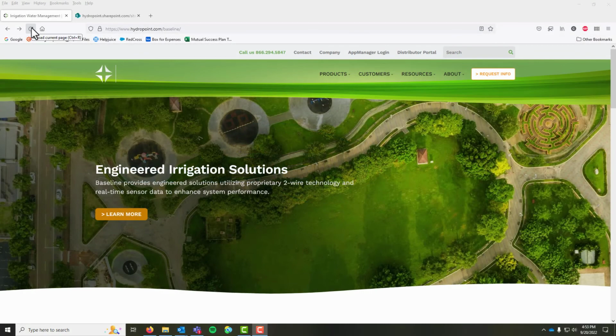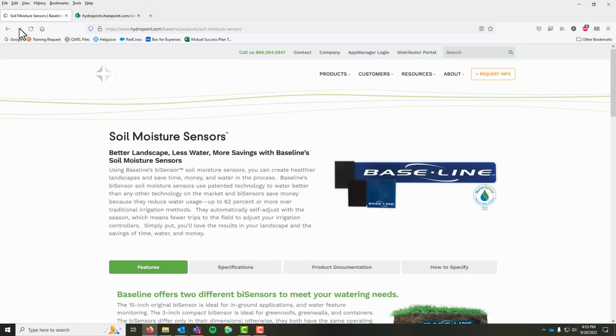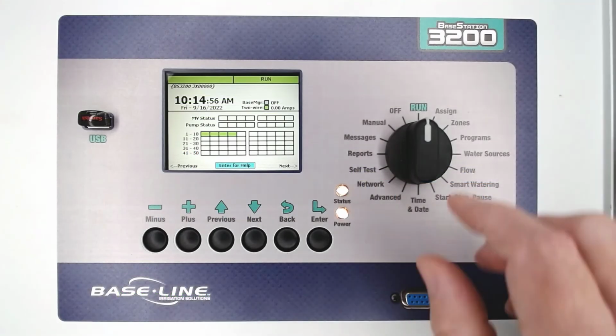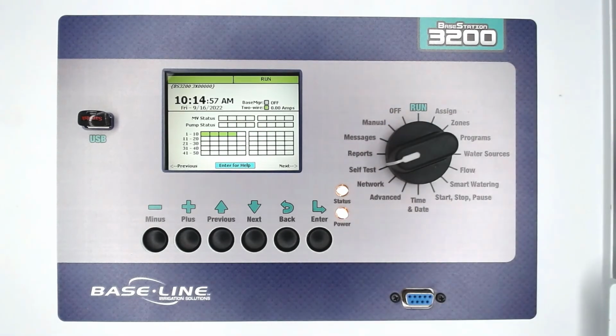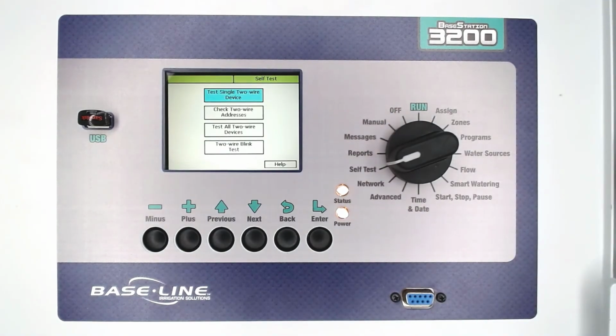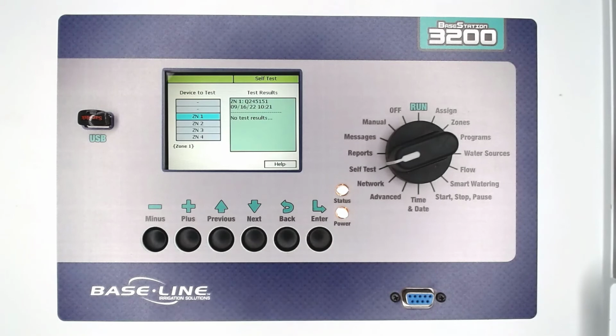This video will help you diagnose and troubleshoot your baseline soil moisture sensor that fails to recognize soil moisture. From the controller, turn the dial to the self-test position. Highlight the menu Test Single 2-Wire Device and press Enter to open that menu. Here I can test any device that's been assigned during the search and assign process.